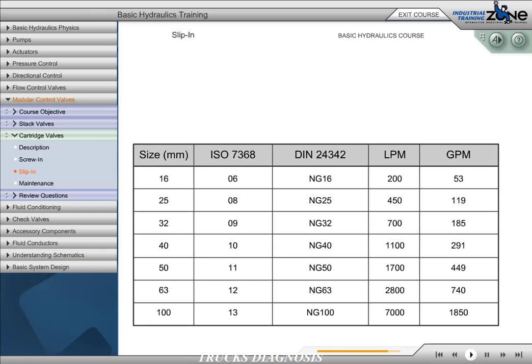In accordance with ISO 7368 or DIN 24342, slip-in cartridge valve configurations are rated by size in millimeters. This table shows valves for slip-in cartridges ranging in size from 16 millimeters to 100 millimeters. Each valve has a nominal flow rating measured as flow through the valve at a pressure drop of 72 PSI. For example, at 72 PSI, a 25 millimeter valve would have a nominal flow rating of 119 gallons per minute.